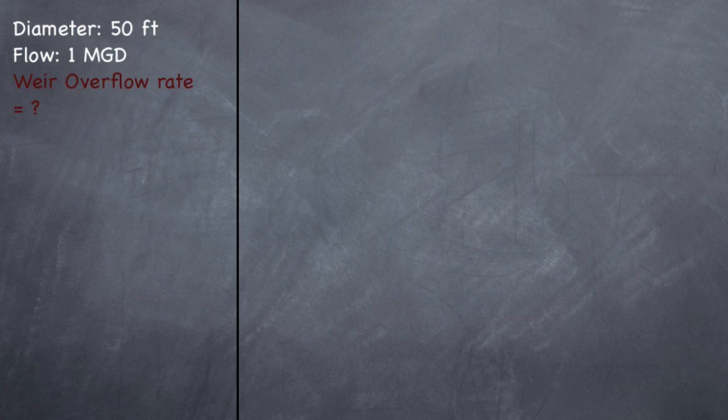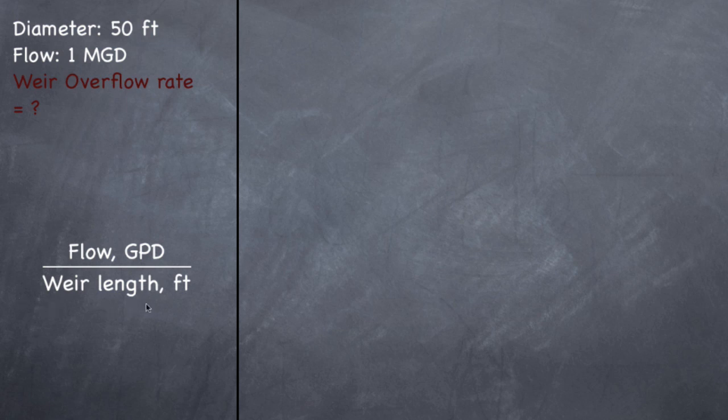Weir overflow rate. This is how much water is going over your weirs of a clarifier per linear foot of weir length. So you need to find out how long your weir is and then divide it into your flow. So the formula for weir overflow rate is flow in gallons per day divided by your weir length in feet. Now, remember what I said earlier? Anytime you see diameter or circumference, that is a circle. And I use circles because they're the most common ones that they use because they're slightly harder than squares.